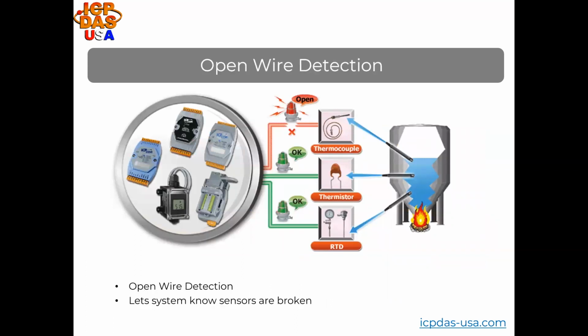Our thermocouple, RTD, and thermistor modules offer open wire detection that helps with system safety. In many applications, it's dangerous when systems cannot remotely monitor the open wire sensor status. When sensor wires are broken, the controller won't know what the temperature levels are, which often causes the system to overheat, resulting in fire or explosions. Our thermocouple, RTD, and thermistor sensors help keep systems safe.